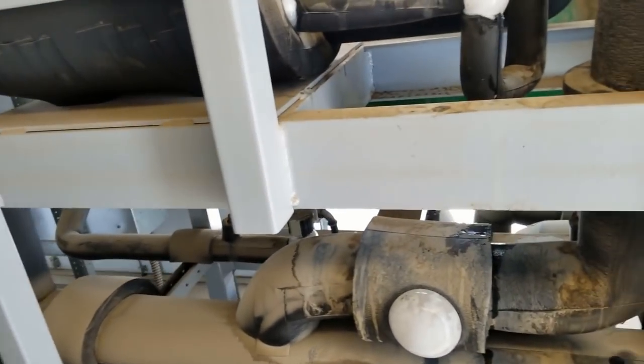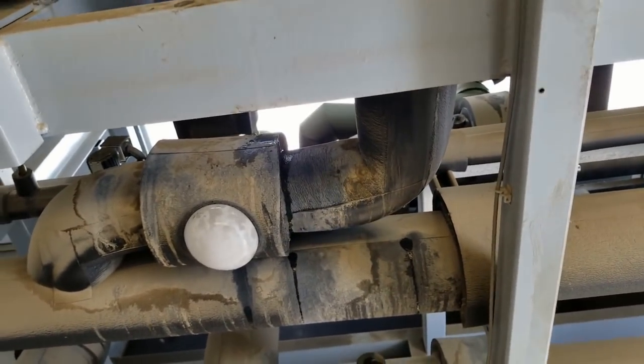We're not getting enough refrigeration going in here. Maybe it has something to do with that compressor. I'll check the suction set points to make sure it's holding suction, but we'll take a look at that.